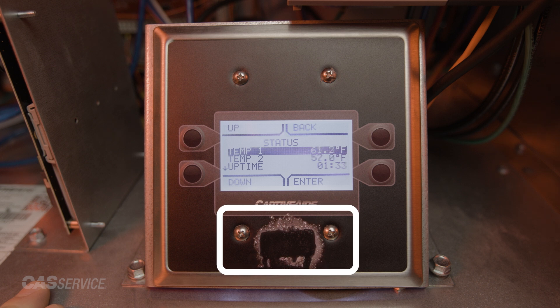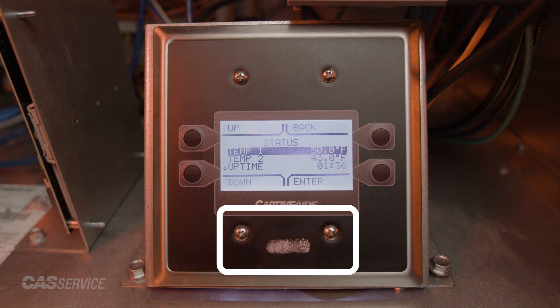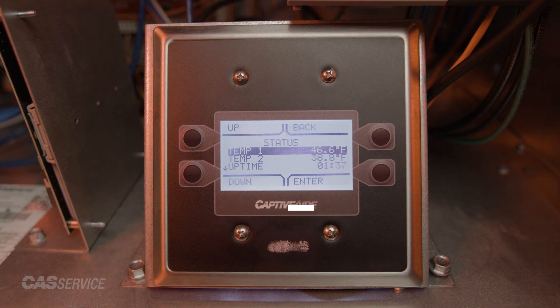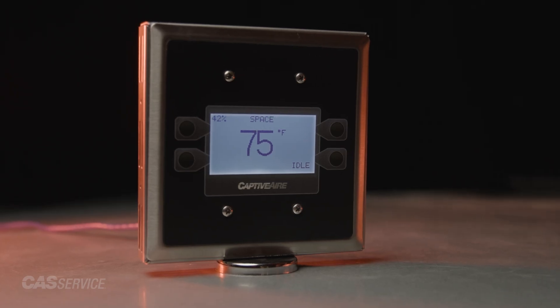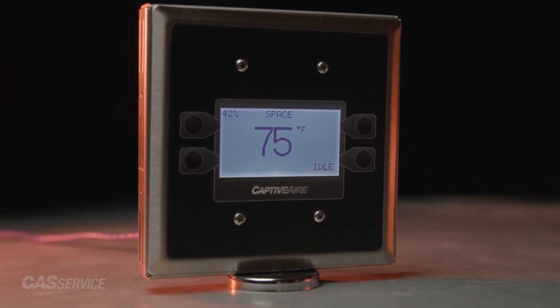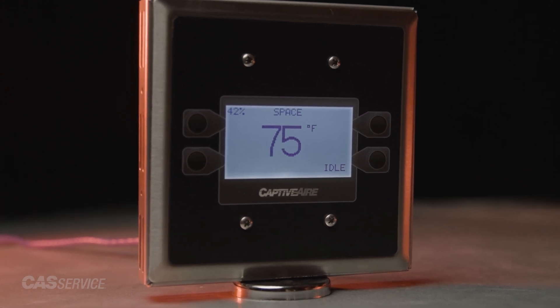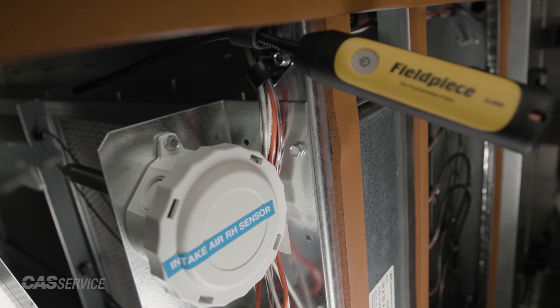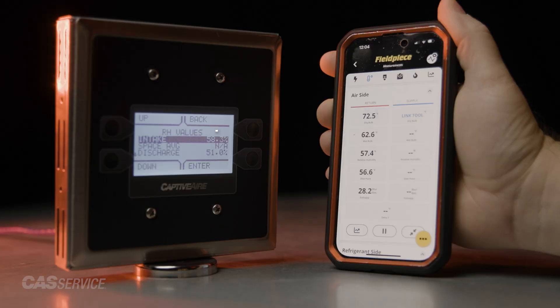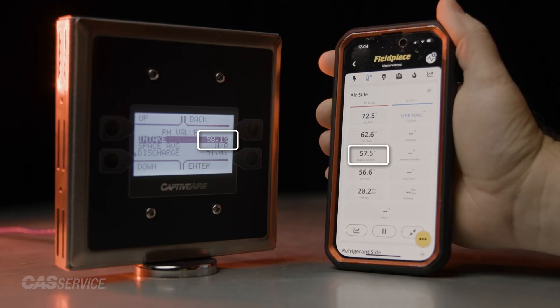Each HMI's temperature is sampled by two adjacent sensors located near the bottom of the faceplate, between the lower two mounting screws. The HMI also has an integrated relative humidity sensor that will sample and display the humidity relative to the current dry bulb temperature. Each of these sensor readings should be compared to test equipment such as a thermometer and psychrometer to verify reading accuracy.